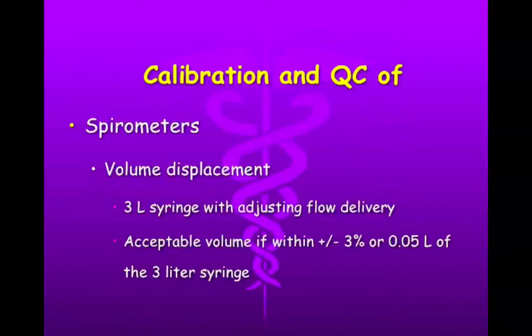If we want to look at our calibration and QC spirometers, well, how do we do that? Well, we use a 3-liter syringe and we adjust the flow delivery. We will deliver it really fast. We'll deliver it really slow. And it should meet within this certain range. There's always a plus or a minus when you're dealing with controls. They're never going to always be exact, like it's going to be an exact pH or it's going to be an exact volume. We have to allow for just some minute errors because we don't live in a perfect world.